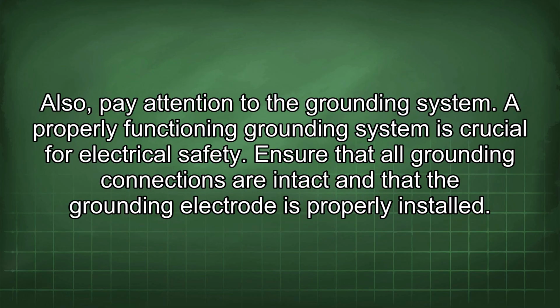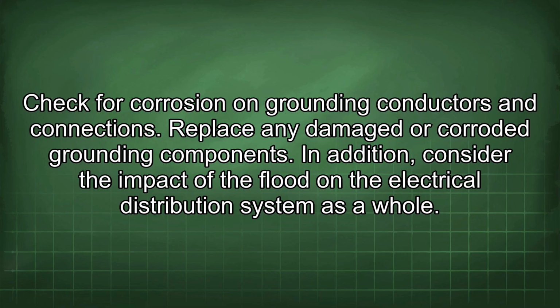Also, pay attention to the grounding system. A properly functioning grounding system is crucial for electrical safety. Ensure that all grounding connections are intact and that the grounding electrode is properly installed. Check for corrosion on grounding conductors and connections. Replace any damaged or corroded grounding components.